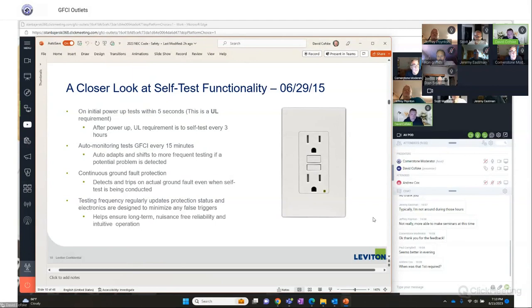But I put a date up there, June 29th, 2015. The NEC and NFPA basically said we want a device that is self-test. So from that date, no manufacturer could manufacture a GFCI device that wasn't self-test. Anything that's installed in a house right now, or was available to buy in a store, was grandfathered in, and you could install those in a residential house. But after 6/29/15, all devices are self-test. You can read the bullet points. As soon as you power up, within 5 seconds, it goes through a self-test to make sure that there's GFCI protection in the device. And then every 15 minutes, it goes through a cycle and rechecks.